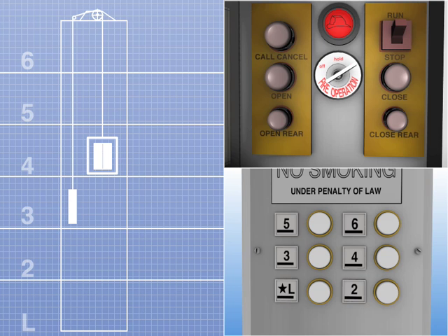The stop switch located in the fire operation panel functions like any other stop switch. It will cause the power to be disconnected from the drive machine and cause the elevator to stop. Unlike the in-car stop switch or the emergency stop switch, this stop switch is not overridden on Phase 1 elevator recall. The elevator will come to an emergency stop when this switch is activated, and any registered car calls will extinguish. When the switch is restored to the run position, the elevator is not allowed to move, except for leveling, until a car call is registered.